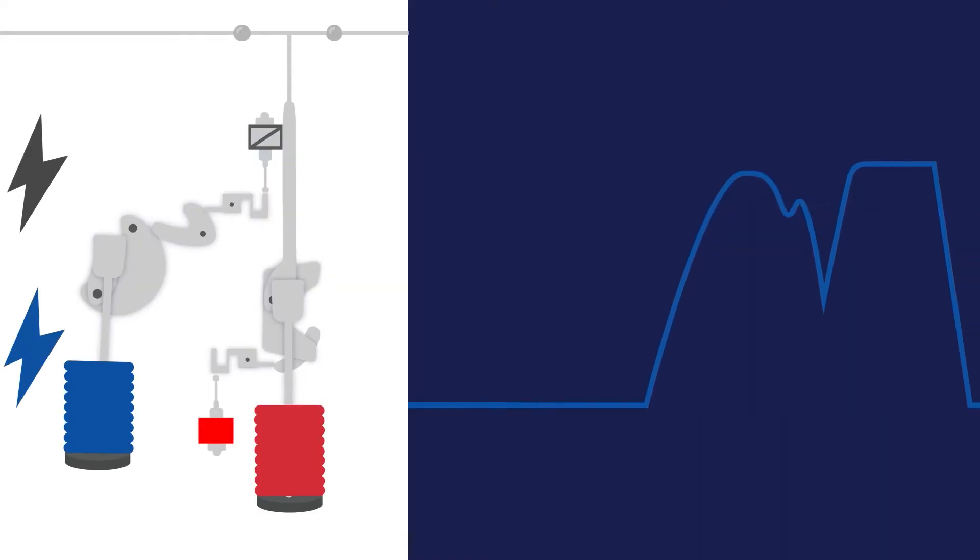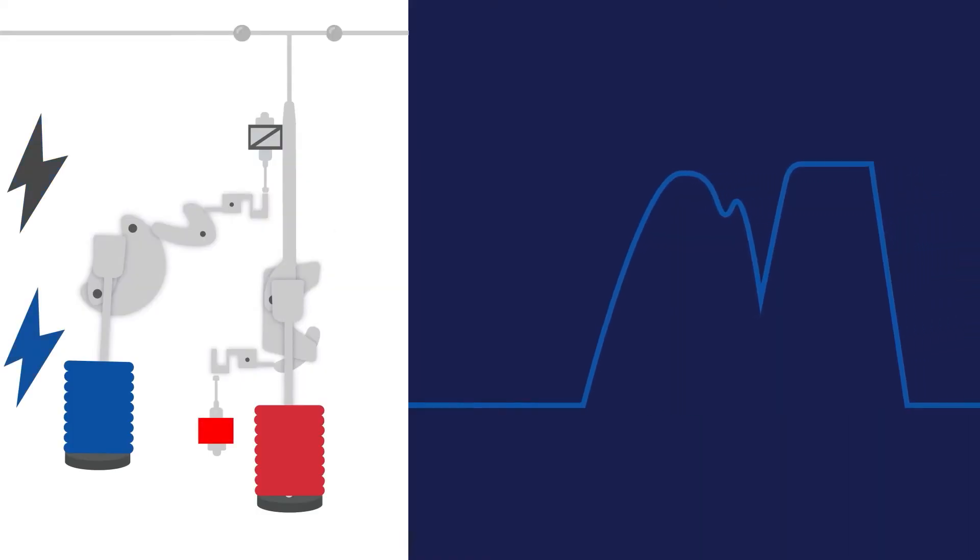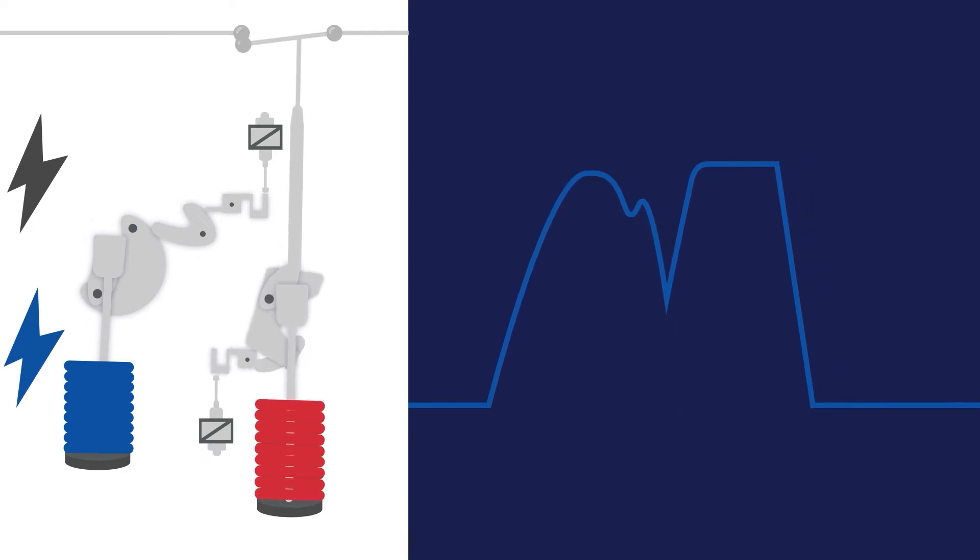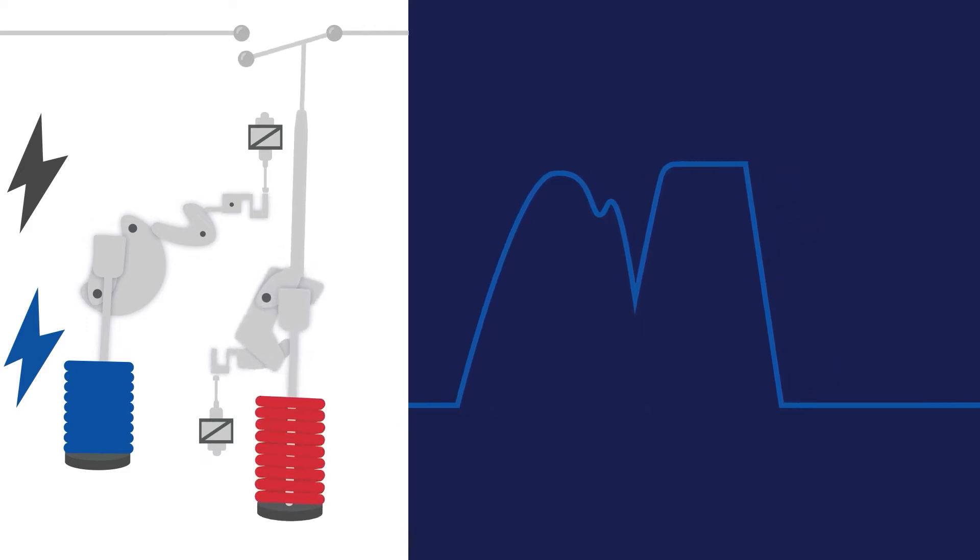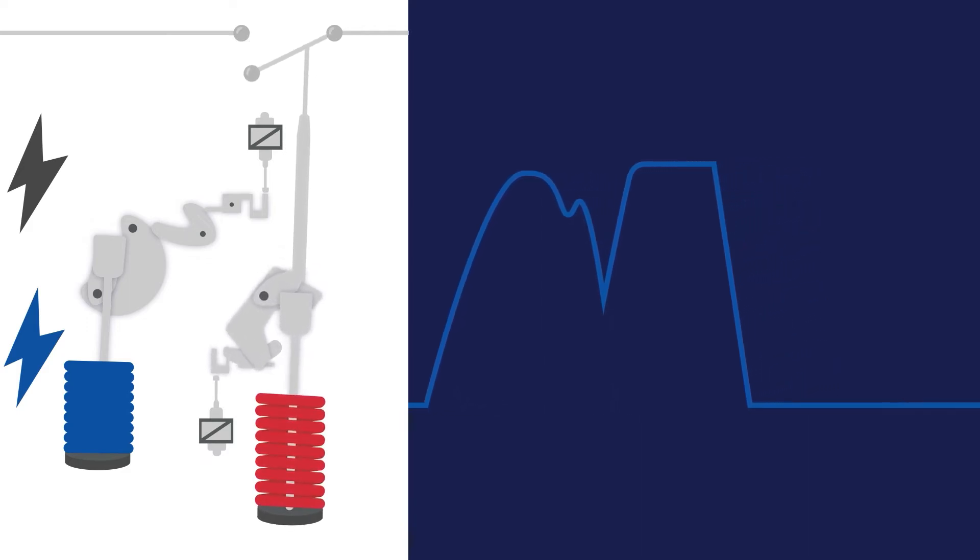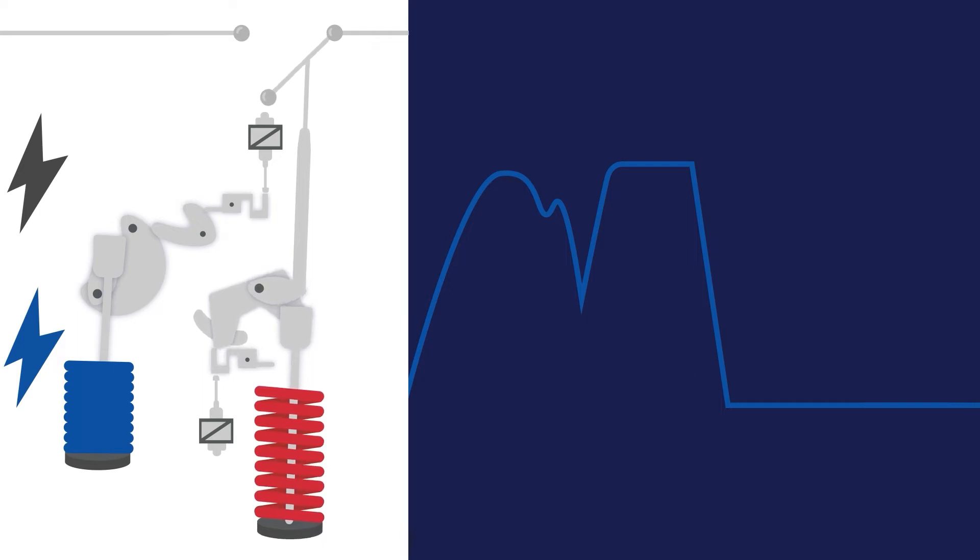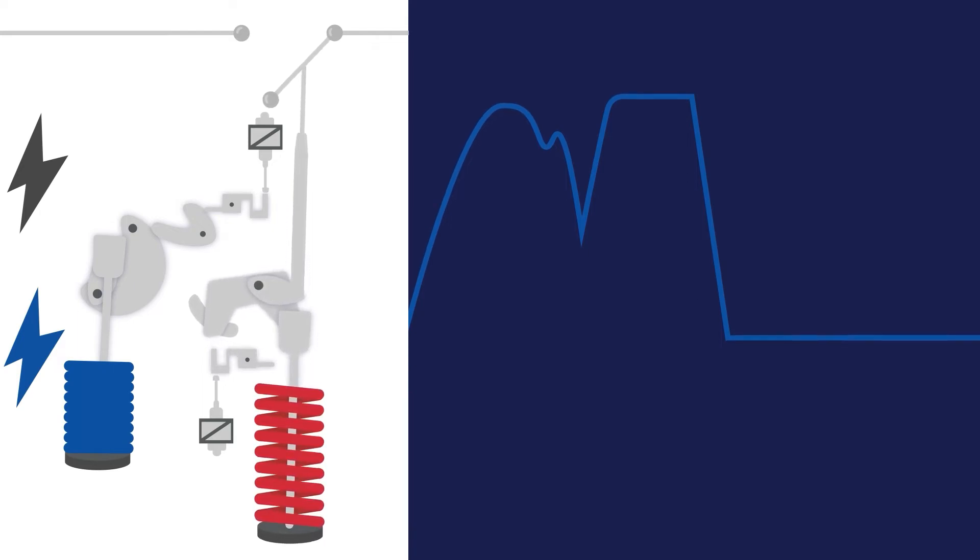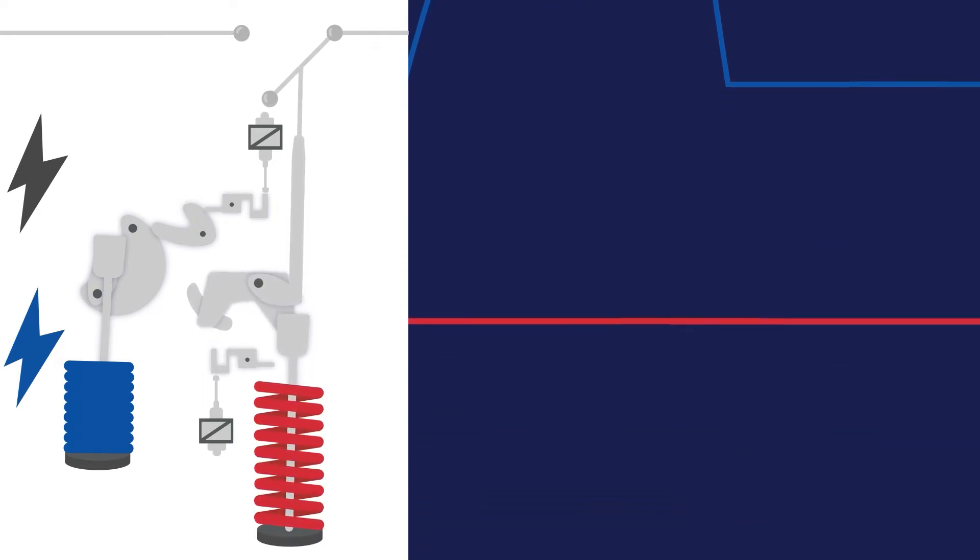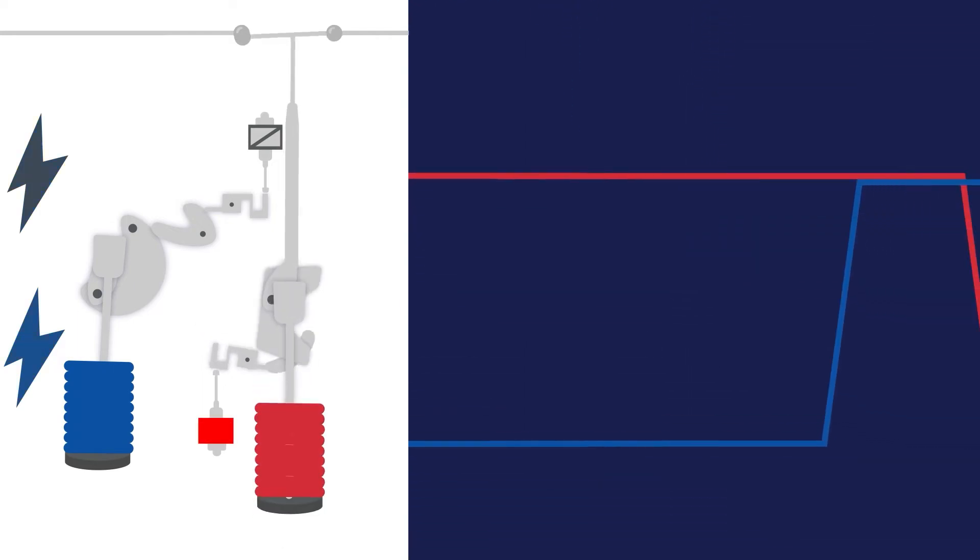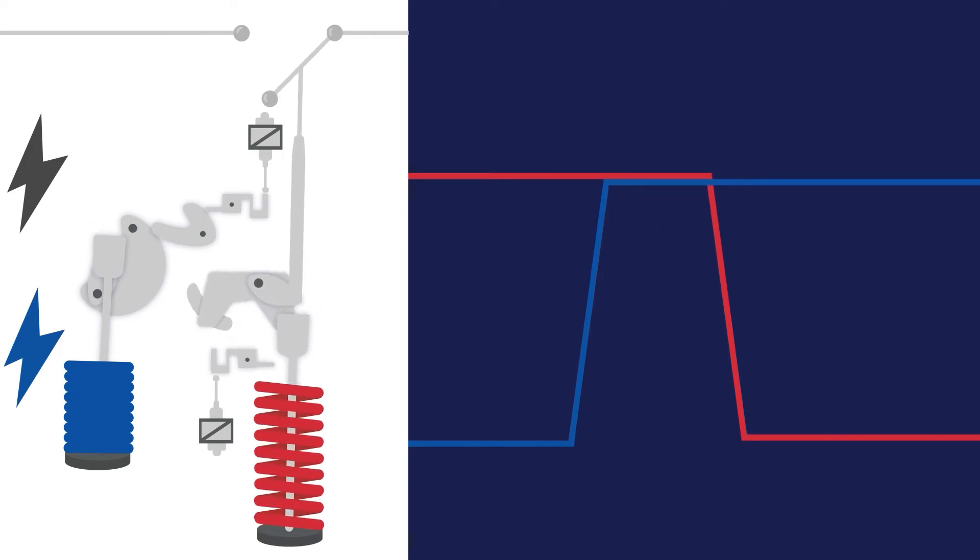This opening of the 52A switch can be viewed in the waveform as the falling edge of the coil current which should return to zero once the operation is completed. This changing of the state of the auxiliary contacts is also captured during the waveform capture as well as the current flow through the breaker's main contacts.